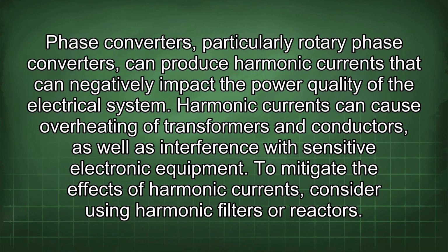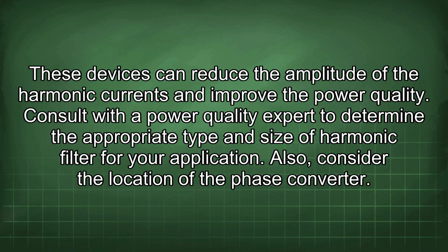Phase converters, particularly rotary phase converters, can produce harmonic currents that can negatively impact the power quality of the electrical system. Harmonic currents can cause overheating of transformers and conductors, as well as interference with sensitive electronic equipment. To mitigate the effects of harmonic currents, consider using harmonic filters or reactors. These devices can reduce the amplitude of the harmonic currents and improve the power quality. Consult with a power quality expert to determine the appropriate type and size of harmonic filter for your application.